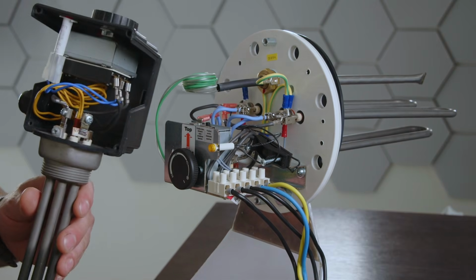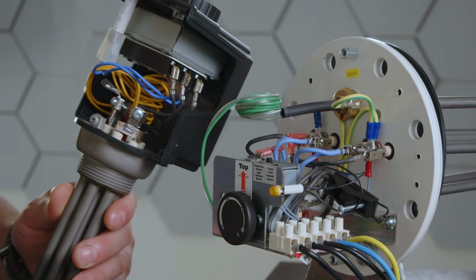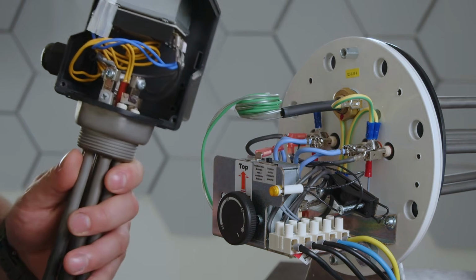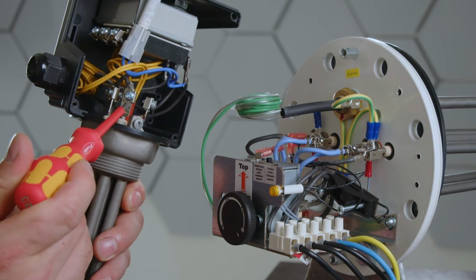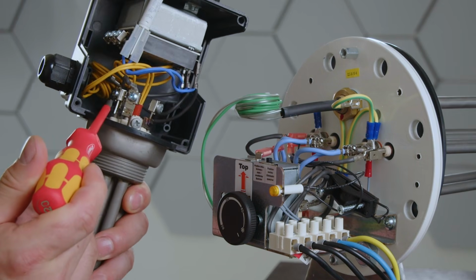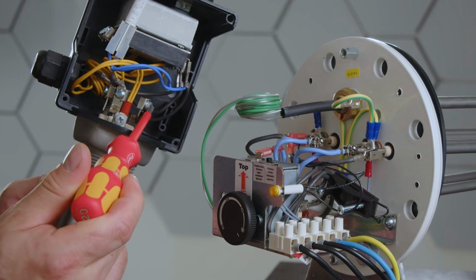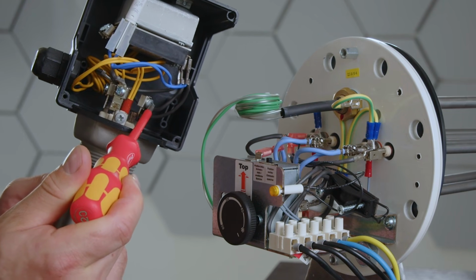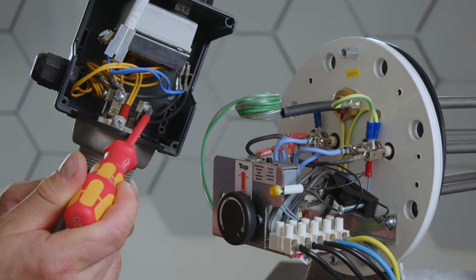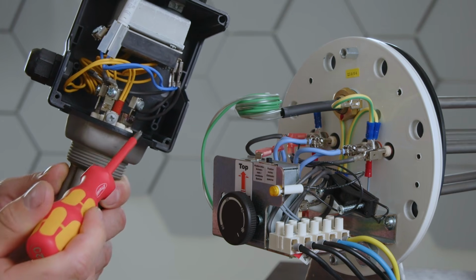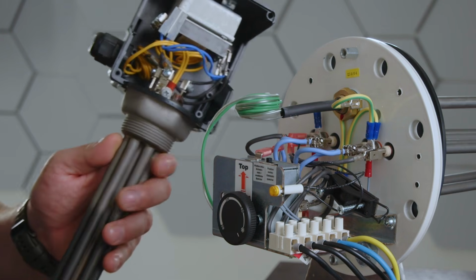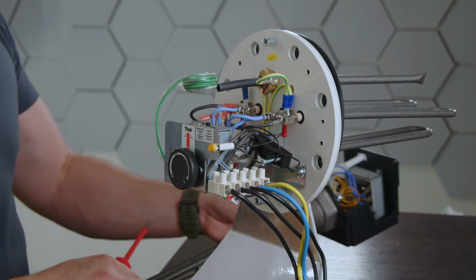One more example would be with this, a little bit simpler heating rod here. We see the three connections for the phases, and here would be the connection for the star topology for the neutral conductor. Very important to have this. Otherwise you would not be able to use the Ohmpilot.